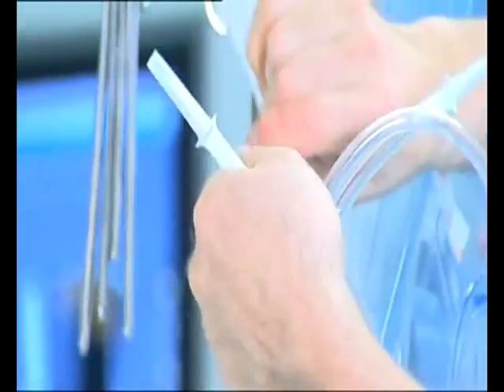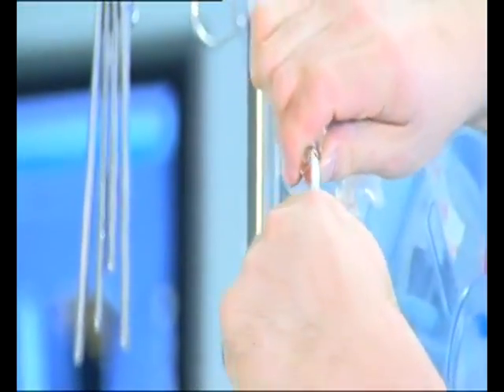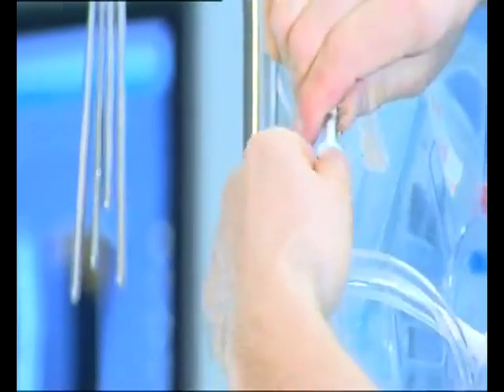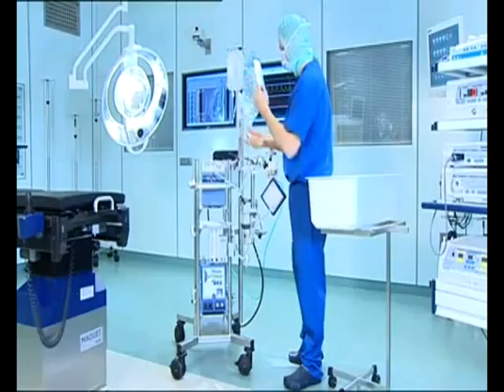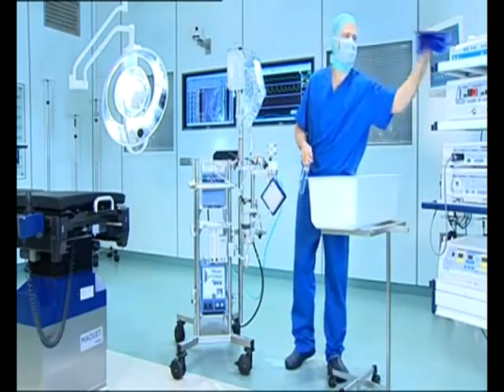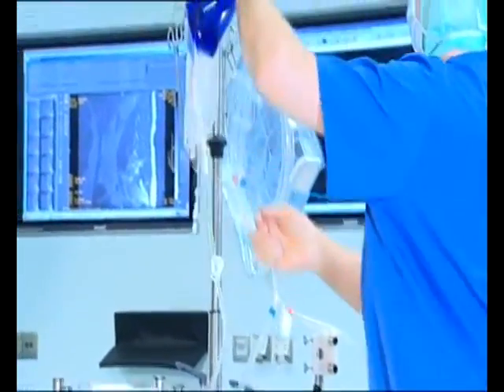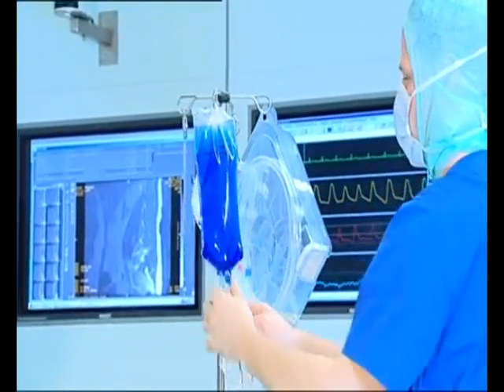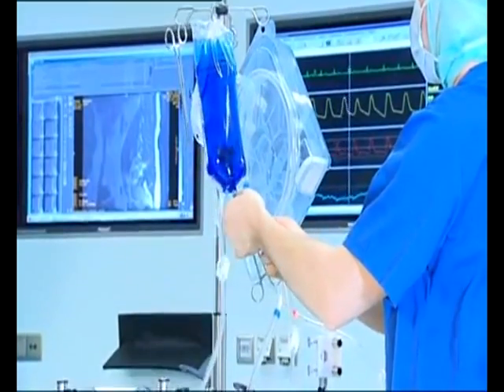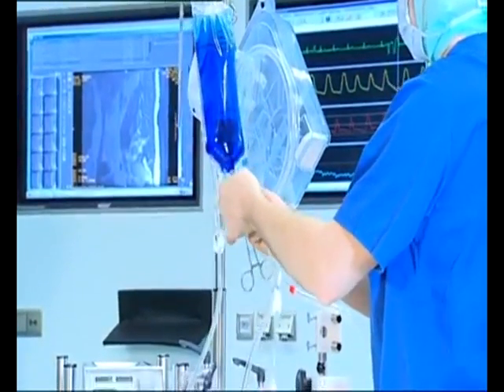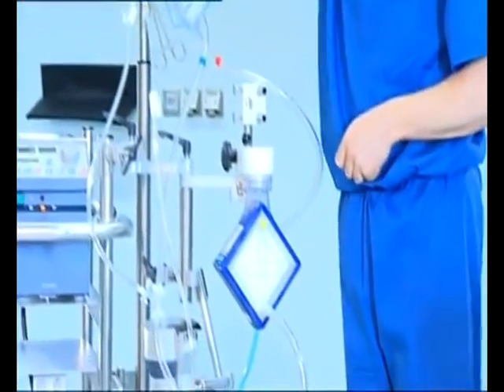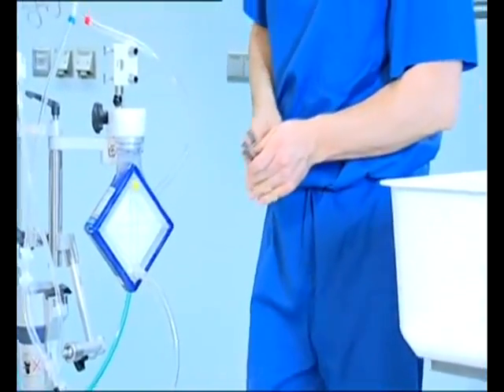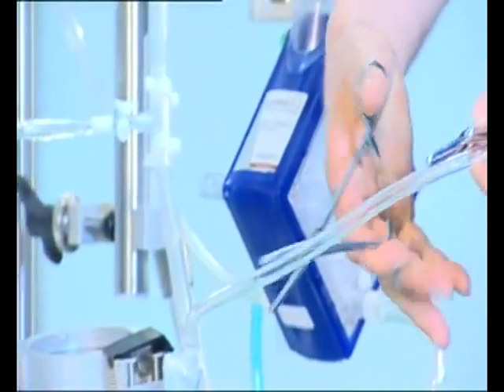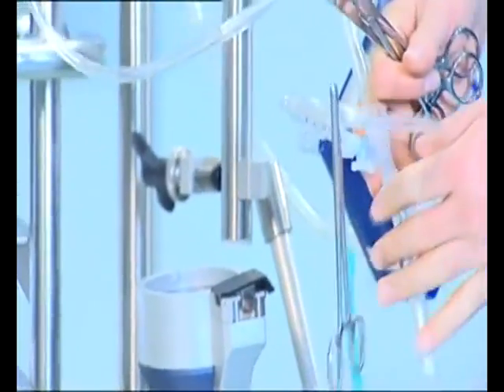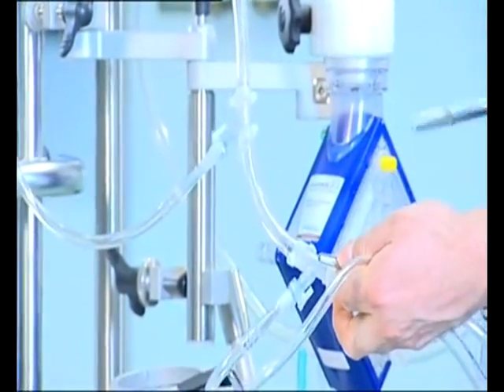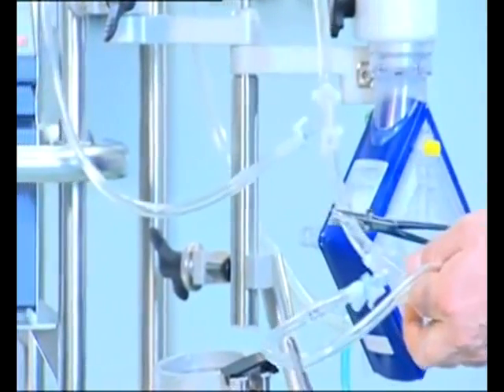The priming line nearest the sterile box is connected to the attached reservoir bag. For demonstration, the priming procedure here is shown with a colored solution and an infusion bag with only one port. The priming line near the centrifugal pump is now connected to the infusion bag. Instead of the accompanying priming bag, an infusion bag with 2 ports can also be used. The priming lines are clamped, and an additional clamp between the 2 connectors will allow circulation of the priming solution into and out of the priming bag system, where air bubbles will be eliminated.